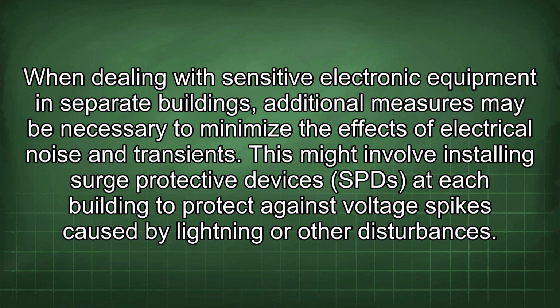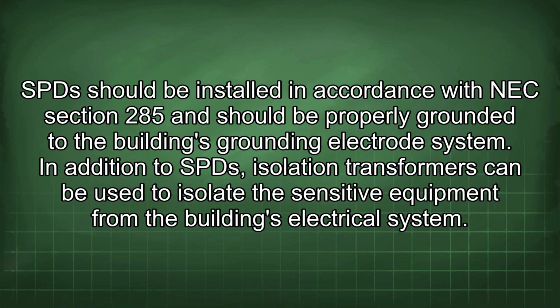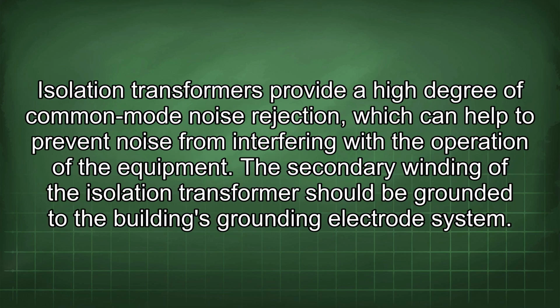When dealing with sensitive electronic equipment in separate buildings, additional measures may be necessary to minimize the effects of electrical noise and transients. This might involve installing surge protective devices (SPD) at each building to protect against voltage spikes caused by lightning or other disturbances. SPDs should be installed in accordance with NEC Article 285 and should be properly grounded to the building's grounding electrode system. In addition to SPDs, isolation transformers can be used to isolate the sensitive equipment from the building's electrical system. Isolation transformers provide a high degree of common mode noise rejection, which can help to prevent noise from interfering with the operation of the equipment. The secondary winding of the isolation transformer should be grounded to the building's grounding electrode system.